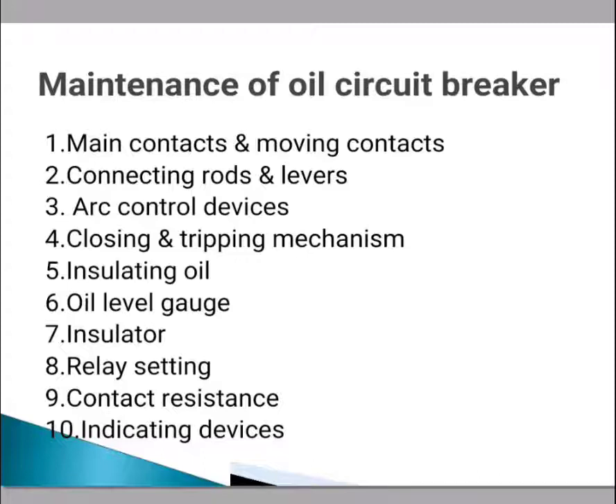For the closing and tripping mechanism, operate the circuit breaker by hand to verify correct mechanism operation. Lubricate the closing mechanism with recommended grade machine oil. Use a firm smooth fabric for cleaning. Replace worn-out parts. This is carried out yearly.